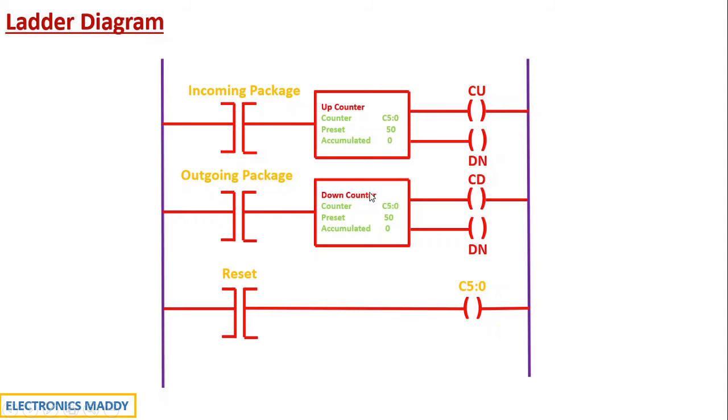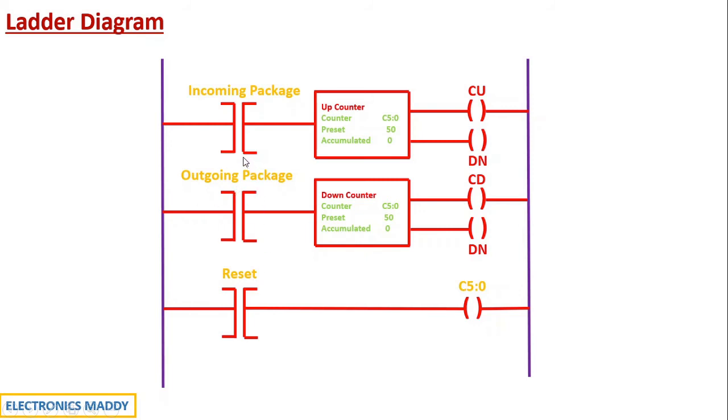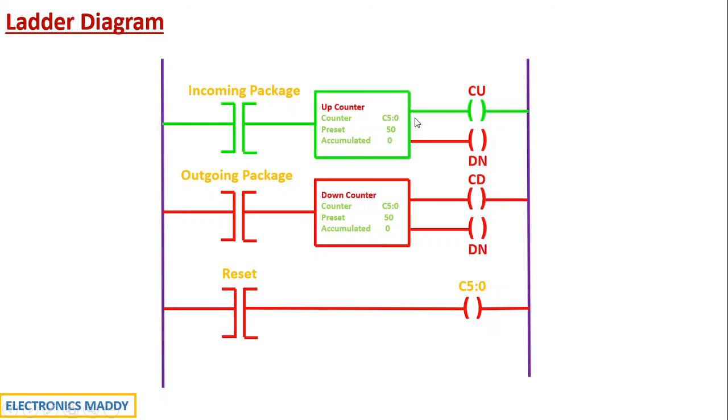So initially when a package enters, these are basically normally open contacts. So these are associated with sensors. Sensor one that we saw is over here and sensor two is with respect to this contact. So whenever a package enters that particular sensor gets activated, the contact gets energized. The rung gets energized, up counter gets energized and correspondingly the counter enable bit actually gets energized instantly.